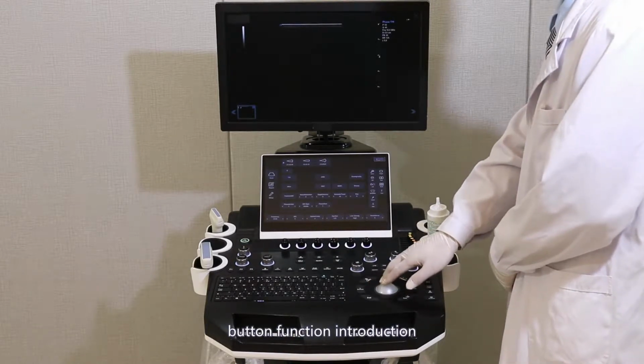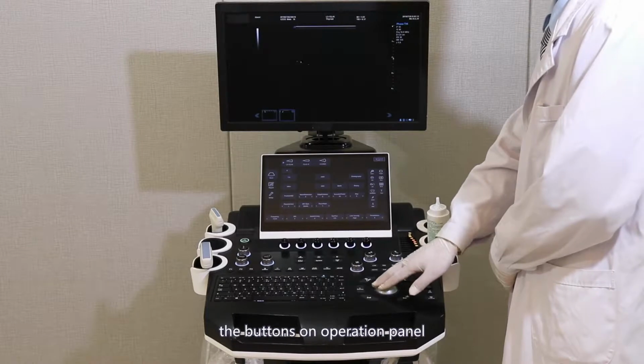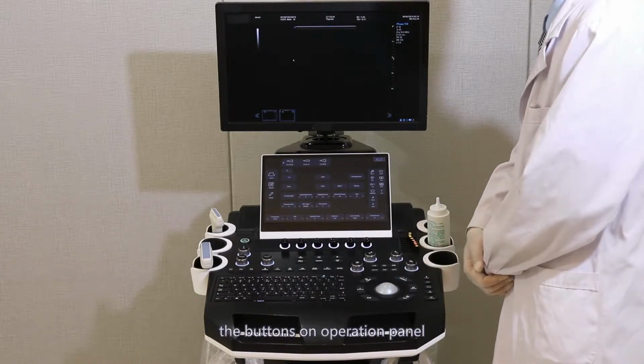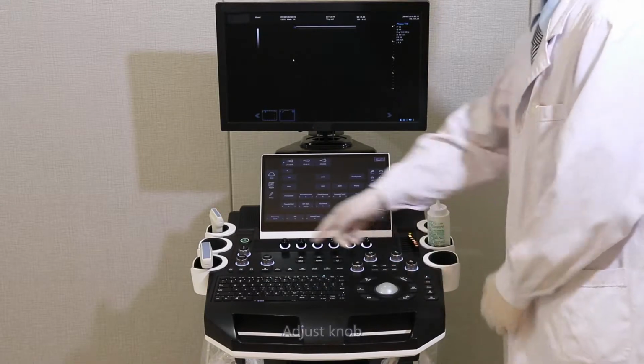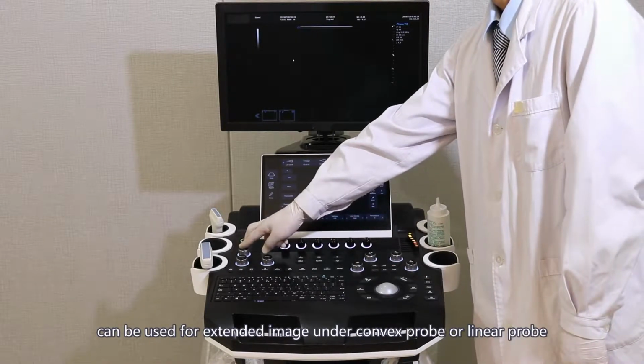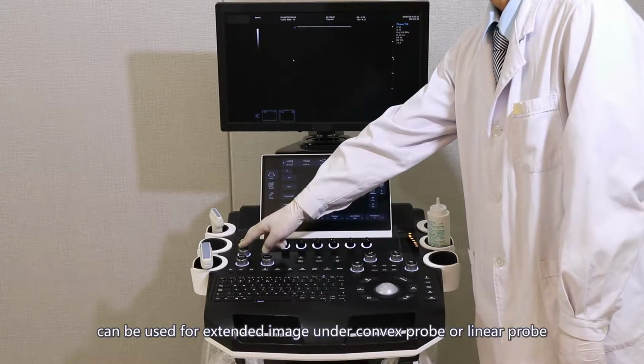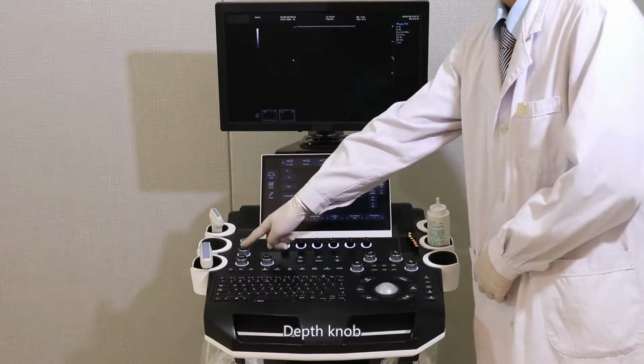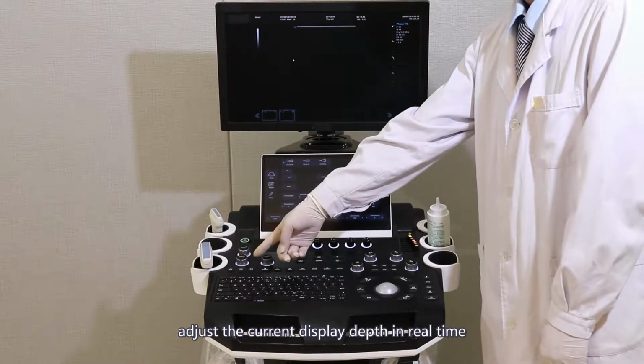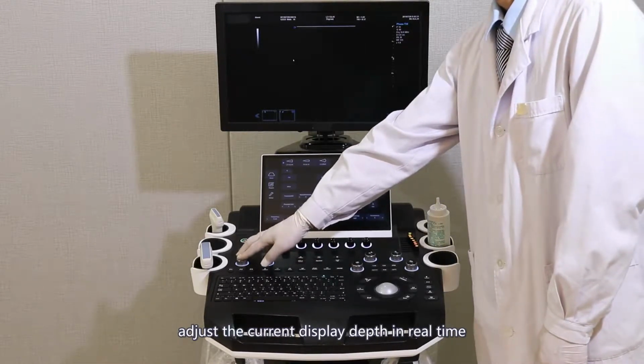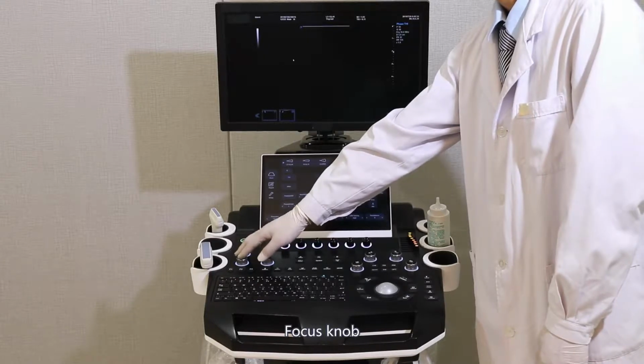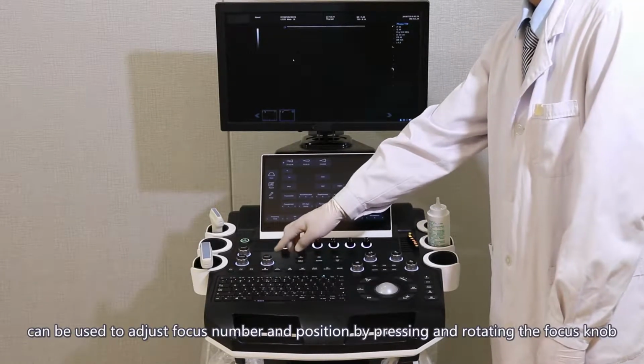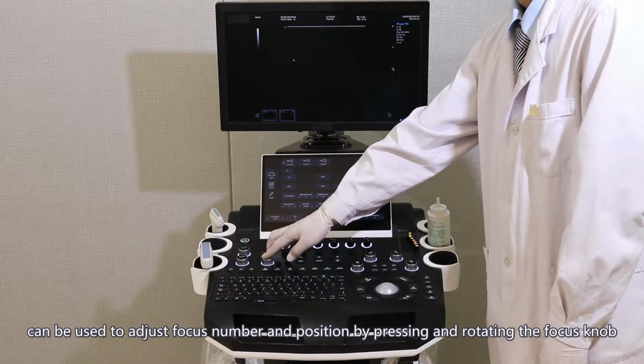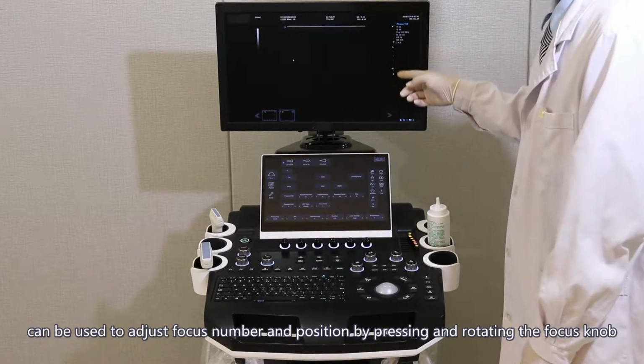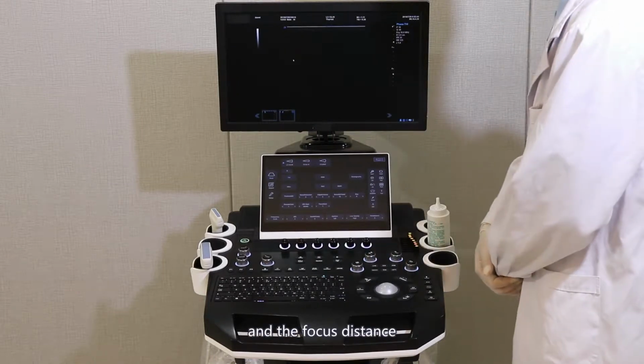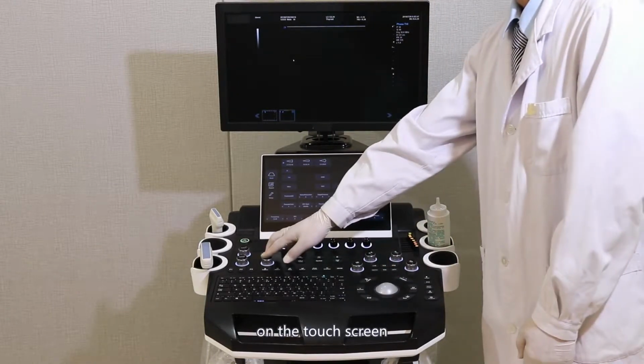Button function introduction. The buttons on operation panel are: adjust knob, can be used for extending image under convex probe or linear probe. Depth knob, adjust the current display depth in real time. Focus knob, can be used to adjust focus number and position by pressing and rotating the focus knob, and the focus distance can also be adjusted on the touchscreen.